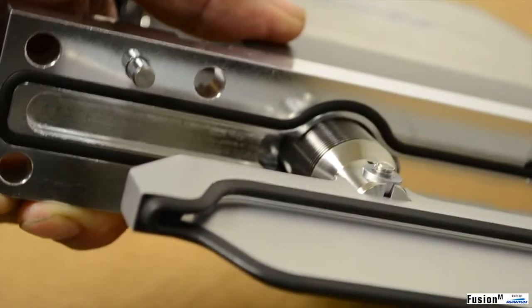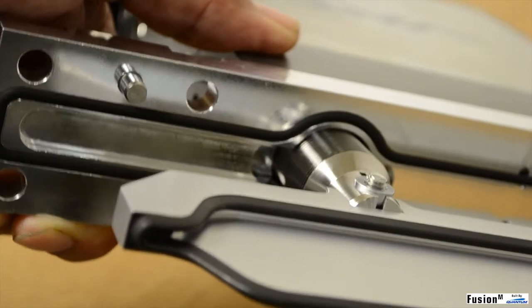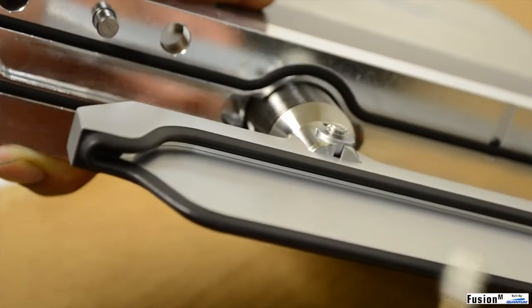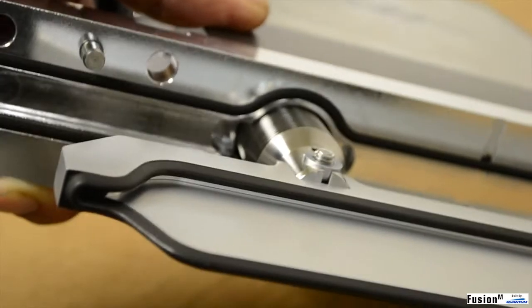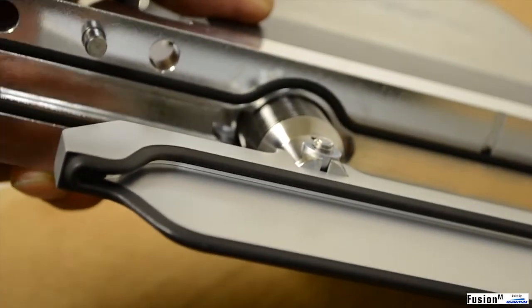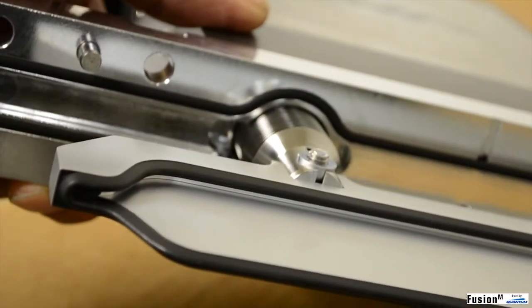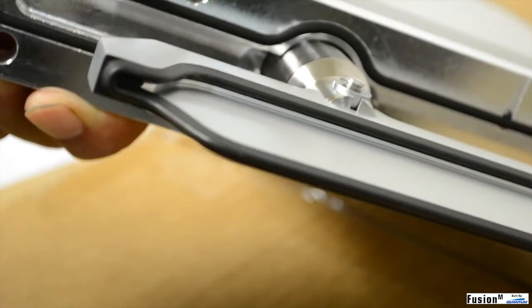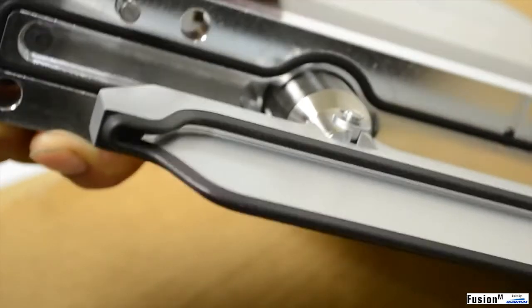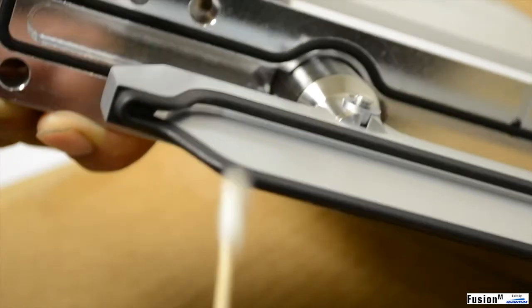I try to stay away from VAT grease on this seal because grease tends to cause things to stick to things, so it's best if you can keep this dry. Now there may come a time when it wears to the point where you may develop a leak and we have to use VAT grease in order to accomplish vacuum. But other than that, we just wipe this down with isopropyl alcohol.